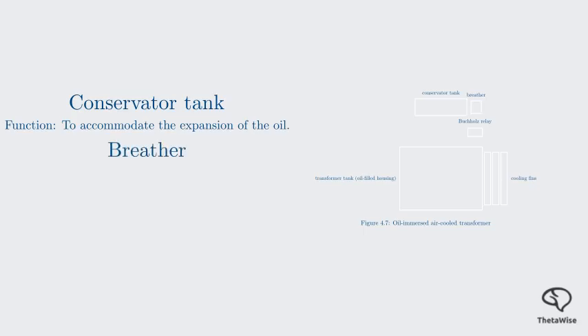Next is the breather, which works in conjunction with the conservator tank. As oil expands and rises into the conservator, it pushes air out. As it cools and contracts, it draws air in. But this air can be moist. Moisture is a transformer's enemy. It degrades the oil and insulation. The breather's job is to ensure that any air entering the conservator tank is completely dry.